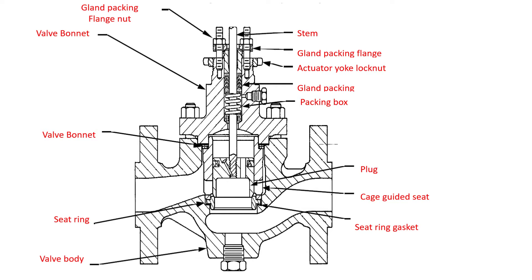We have a bonnet gasket, which provides a seal between the body and the bonnet mating surface. A cage gasket provides a seal between the bonnet and the cage mating surface. Next we have the gland packing. The packing prevents leakage along the valve stem, so the process fluid contained in the trim doesn't leak through the bonnet. The packing is compressed to form a tight seal between the packing box and the valve plug stem by tightening the packing flange nuts. As the nuts are tightened, the packing flange transfers the compressive load to the packing.